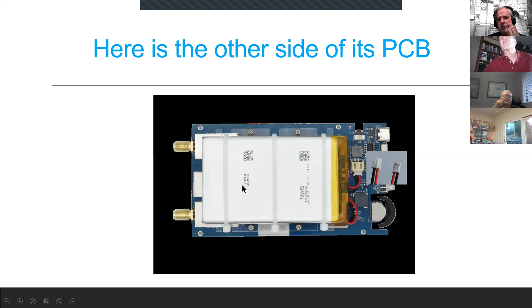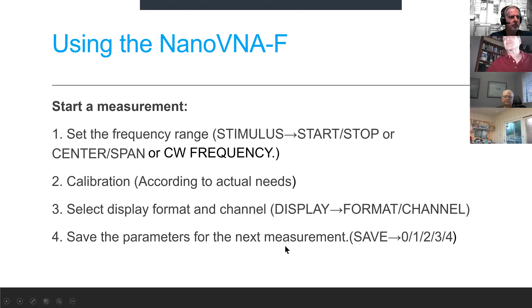So how do you use it? Well, you set the frequency range by going to the stimulus tab, and you either set a start and stop frequency range or a center and span, for example, 100 megahertz plus or minus 20 megahertz, or you go to some CW frequency that you want to measure at. You calibrate it according to your actual needs. You select the display formats that you want to see, for example, the magnitude of S11 in dB, and you save the parameters for the next measurement that you want to do of the same thing in the 5 available registers.